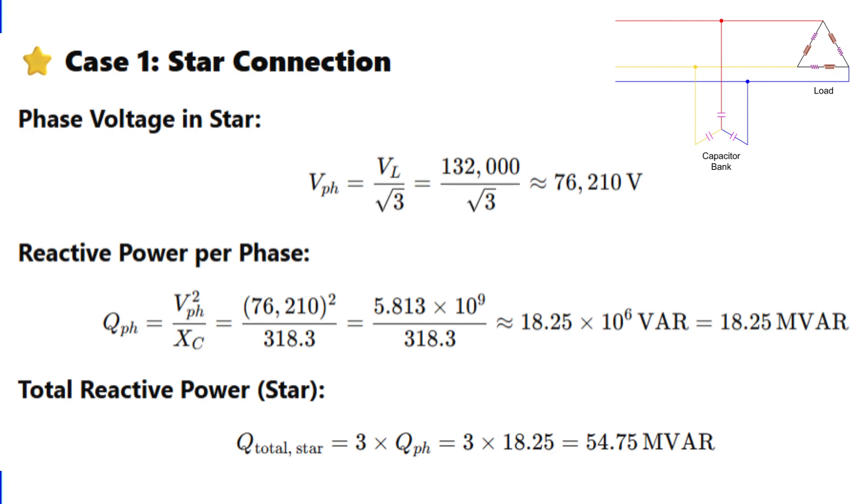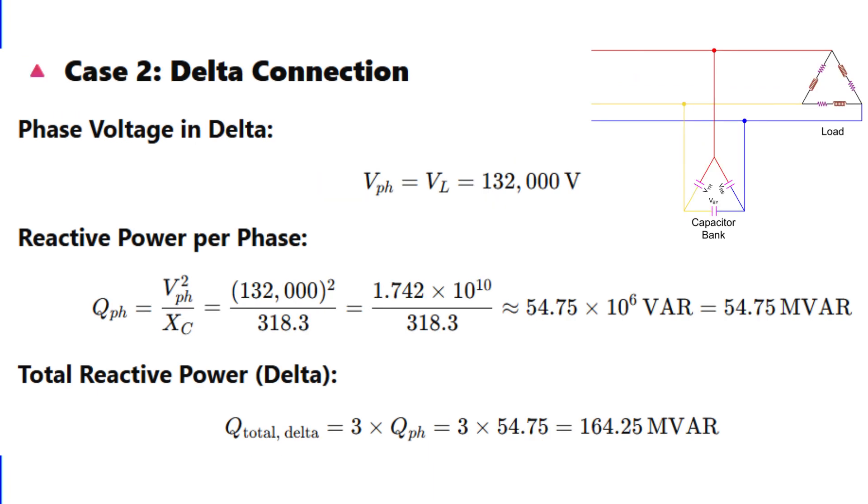Now in delta, each capacitor is connected across two lines, so it gets full line voltage. So V phase is equal to 132,000 volts. Reactive power per phase becomes 132,000 squared divided by 318.3, which gives approximately 54.75 megavolt-ampere reactive per phase. Multiply by three for total and we get 164.25 megavolt-ampere reactive in delta connection. So delta gives three times the reactive power compared to star connection using the same capacitors and same line voltage. That's a massive difference.